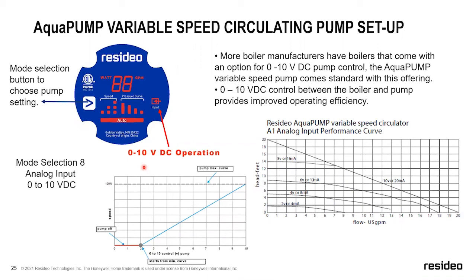So the pump will, as I mentioned with that auto mode, hunt to find the proper flow rate. So I'm a big fan of using this around the boiler loop. The capabilities are there if you want to use it on the system side. I'm not personally a fan of that myself.